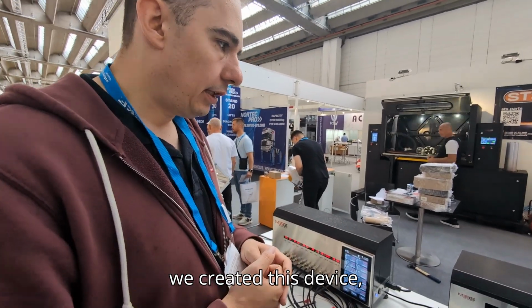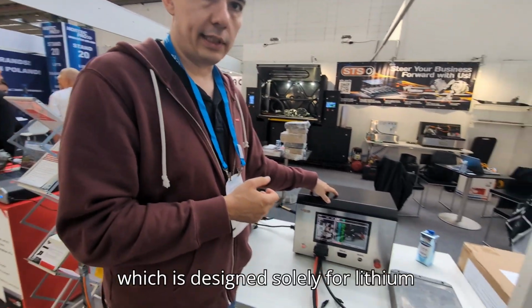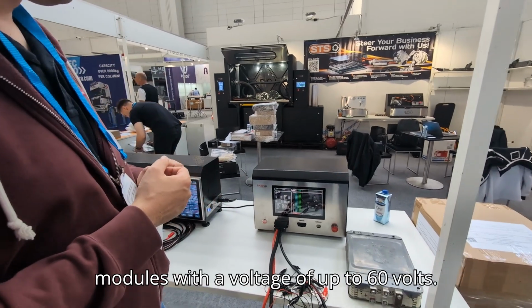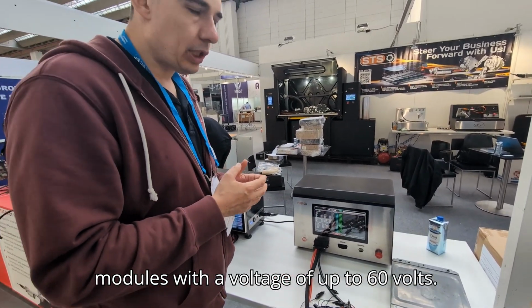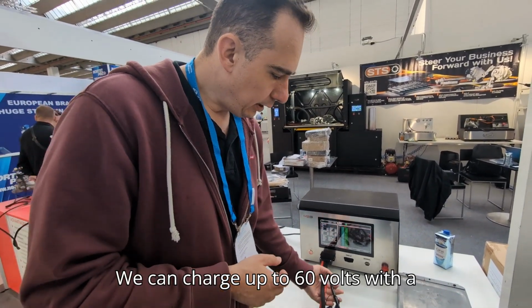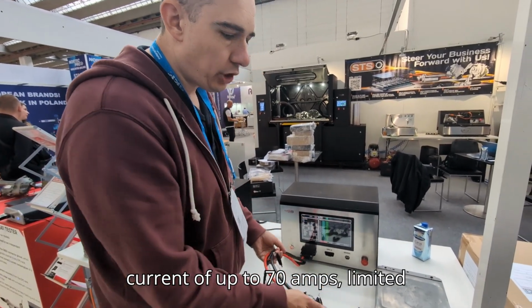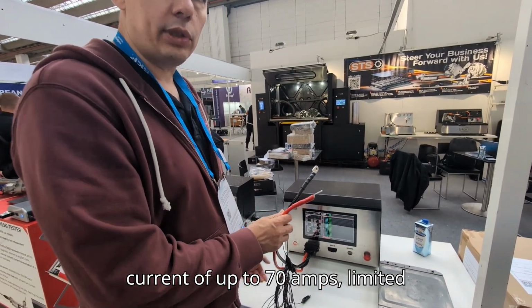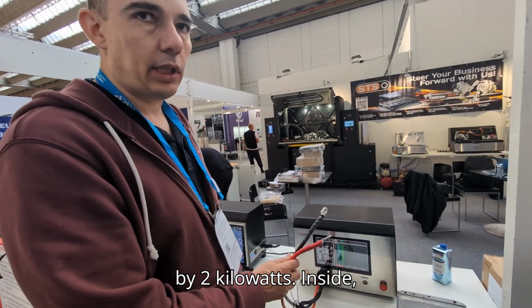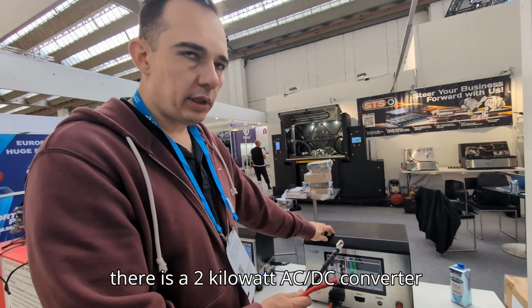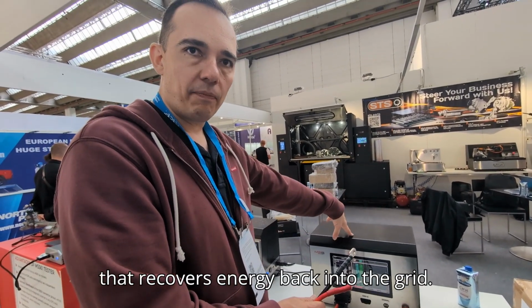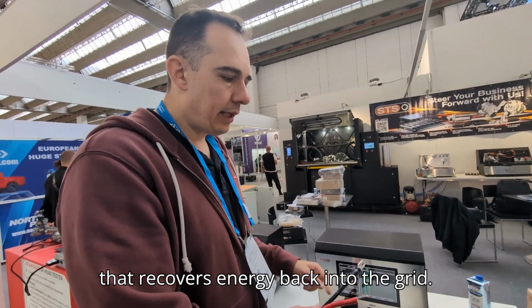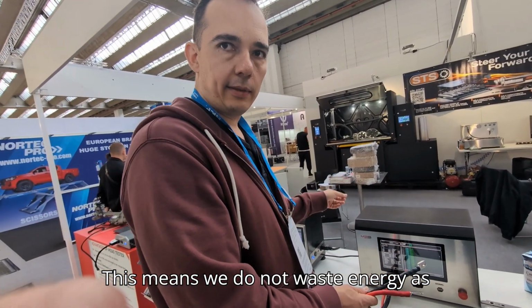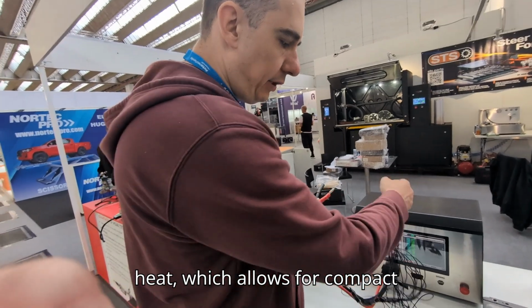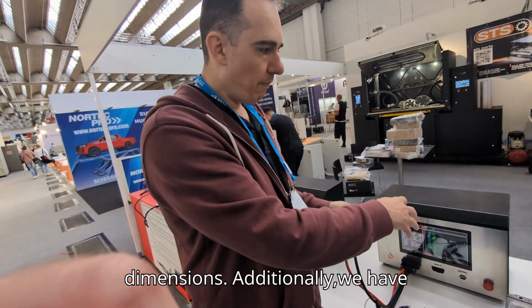To address this, we created this device, which is designed solely for lithium modules with a voltage of up to 60 volts. We can charge up to 60 volts with a current of up to 70 amps, limited by 2 kilowatts. Inside, there is a 2 kilowatt AC-DC converter that recovers energy back into the grid. This means we do not waste energy as heat, which allows for compact dimensions.